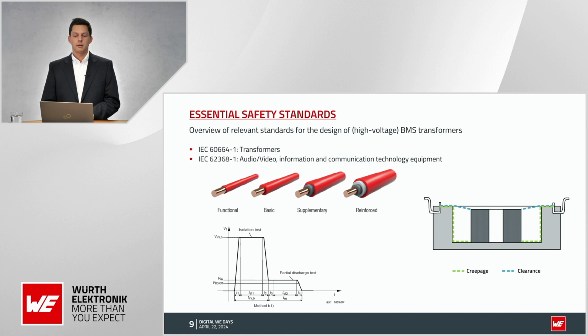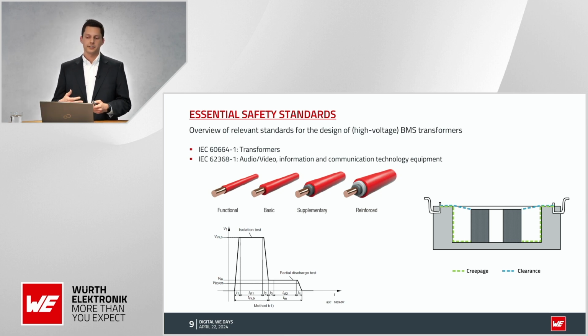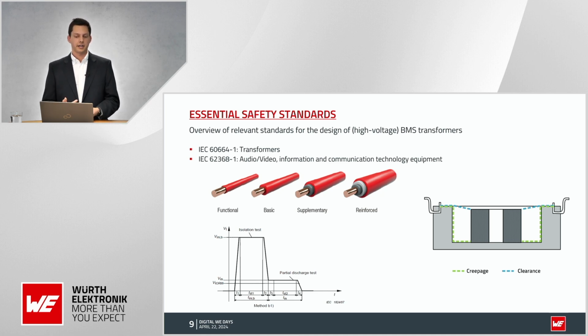Basic insulation provides the user with simple protection against electrical shock. The supplementary isolation goes beyond this basic isolation and provides further protection. Reinforced isolation provides an additional layer that works in a similar way to the supplementary isolation. Even if the basic isolation fails, the supplementary isolation remains effective and protects the user. On the bottom side, you can see a partial discharge test, so here on the left side, which is a good test to test the isolation for working voltages. But I will come back later to this topic on one of the next slides.